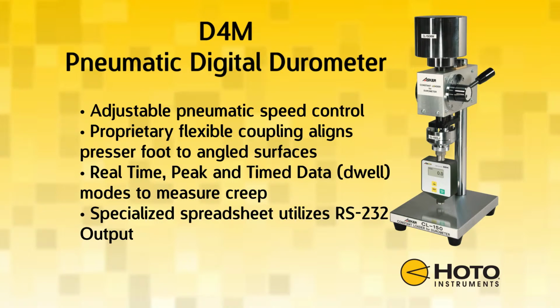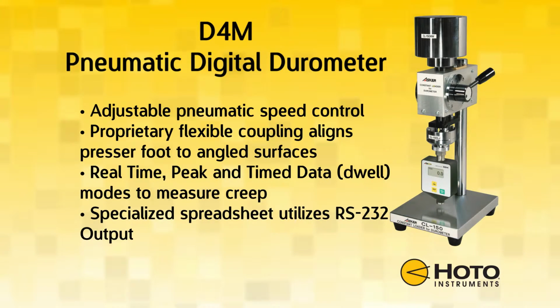The D4M pneumatic digital durometer consists of a digital durometer with a pneumatic constant load stand. The constant load stand features an adjustable air damper for consistent test speeds. The stand also has a proprietary flexible coupling, which aligns the presser foot of the durometer perfectly, even on slightly angled surfaces. The durometer features three different operating modes: real-time, peak, and timed data modes.